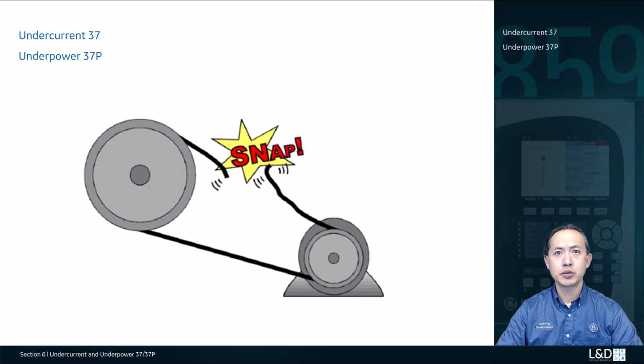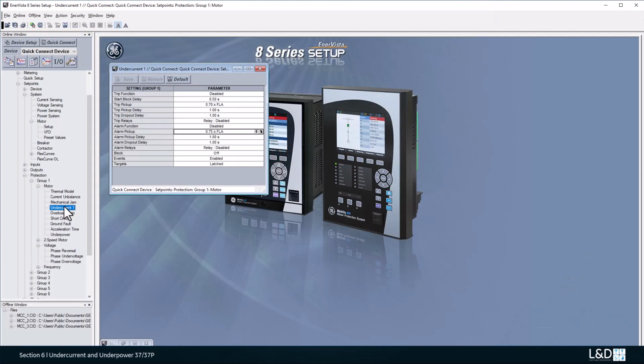Undercurrent and underpower are used to detect the loss of load of the motor, for example, the loss of suction in a pump application or the broken belt in a conveyor application. The undercurrent element responds to a per-phase current. When the motor is in a running state, an alarm occurs if the magnitude of any phase current falls below the undercurrent alarm pickup level for the time specified by the undercurrent alarm delay. Furthermore, a trip occurs if the magnitude of any phase current falls below the undercurrent trip pickup level for the time specified by the undercurrent trip delay. The alarm and trip pickup levels must be set lower than the lowest motor loading during the normal operation.